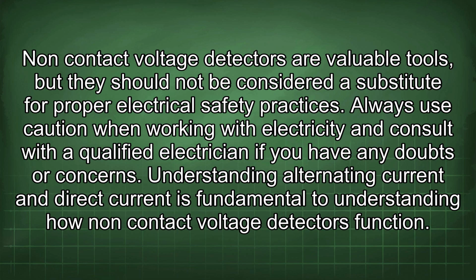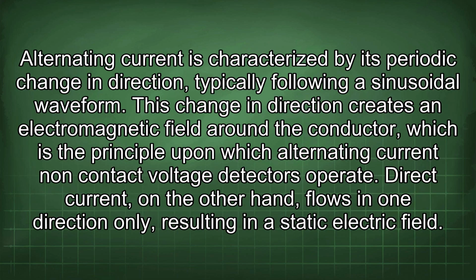Understanding alternating current and direct current is fundamental to understanding how non-contact voltage detectors function. Alternating current is characterized by its periodic change in direction, typically following a sinusoidal waveform. This change in direction creates an electromagnetic field around the conductor, which is the principle upon which alternating current non-contact voltage detectors operate. Direct current, on the other hand, flows in one direction only, resulting in a static electric field.